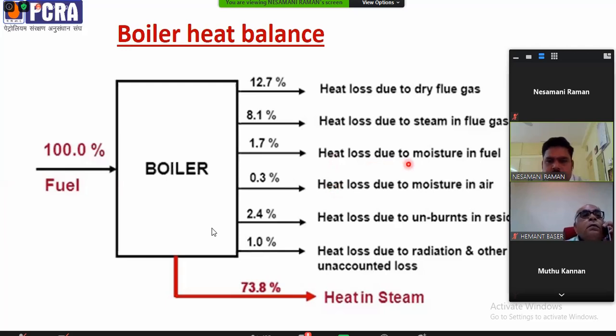Third is heat loss due to moisture in the fuel, which is almost 1.7%. Fourth is heat loss due to moisture in the air, which is 0.3%. Then heat loss due to unburnts in residues. This is for solid fuels, meaning biomass or coal, which is normally at 2.4%, but it will vary obviously. And the radiation and unaccounted loss will be 1%.